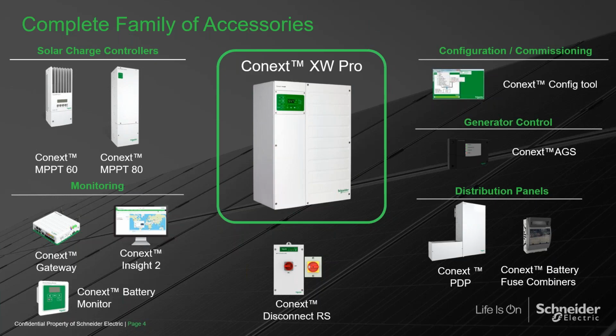DC coupled applications use a charge controller. AC coupled applications, we work with, say, SMA inverters, Enphase inverters. If you look on the left upper corner, you see our charge controller product line. We have an MPPT 60 that's 150 volts open circuit. We have an 80 amp charge controller that's 600 volts, so like a traditional string inverter. And this fall, we're going to be launching a 100 amp charge controller, so another 20 amps, which is roughly a 6 kilowatt PV array.